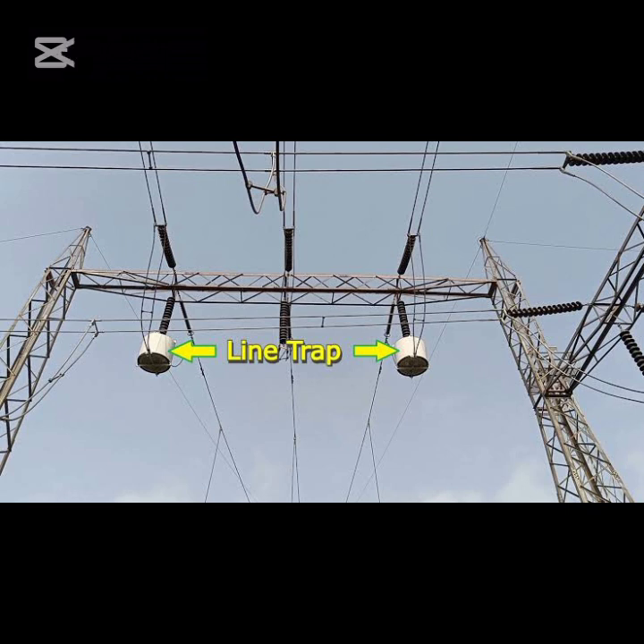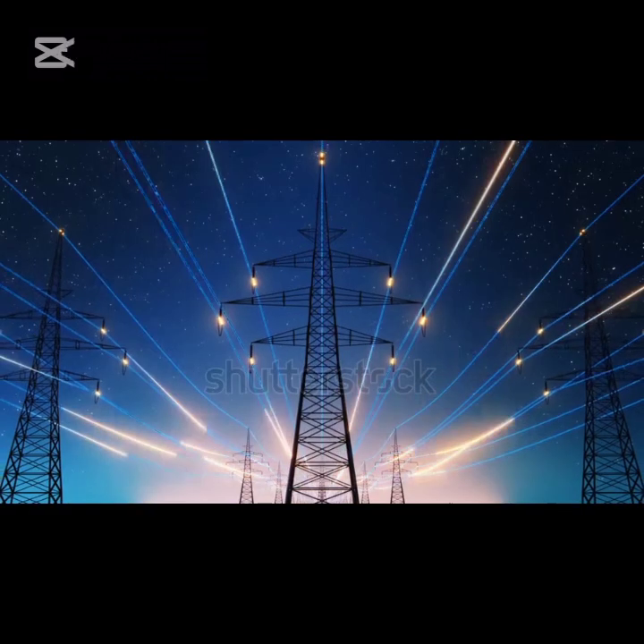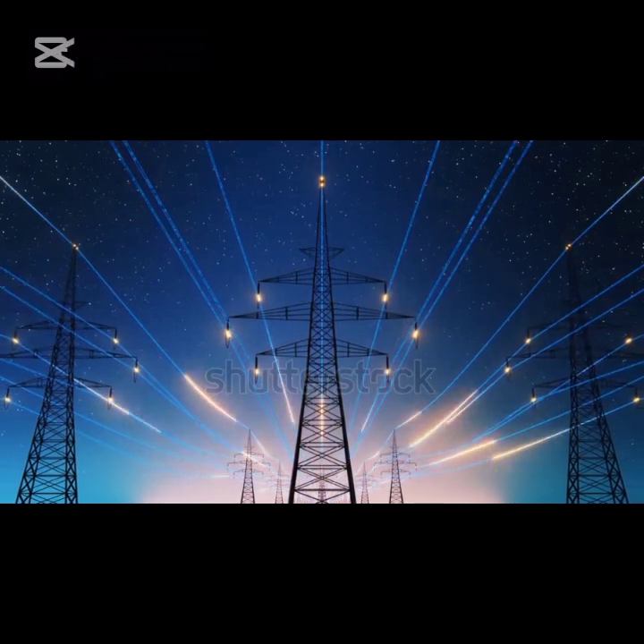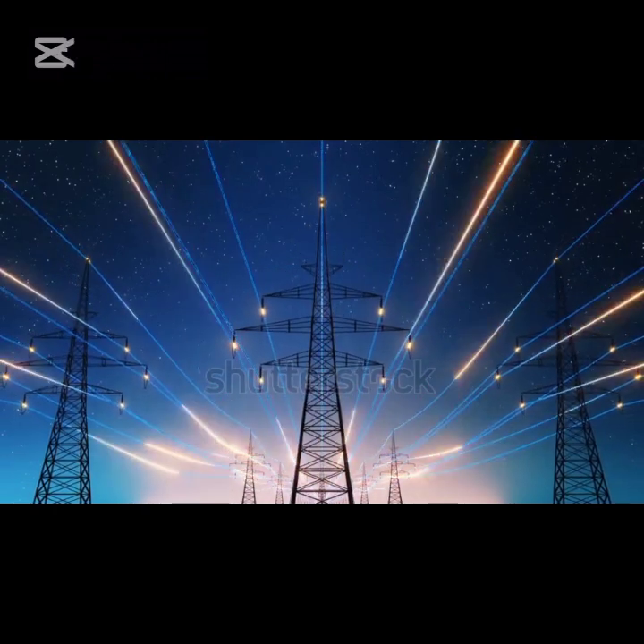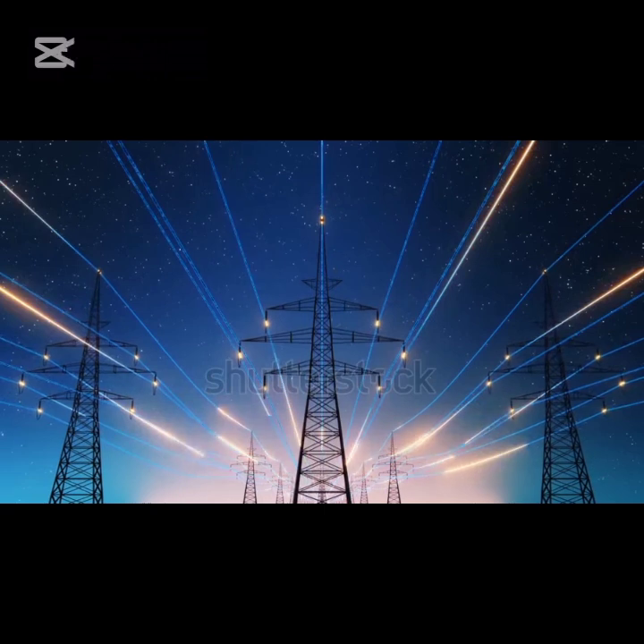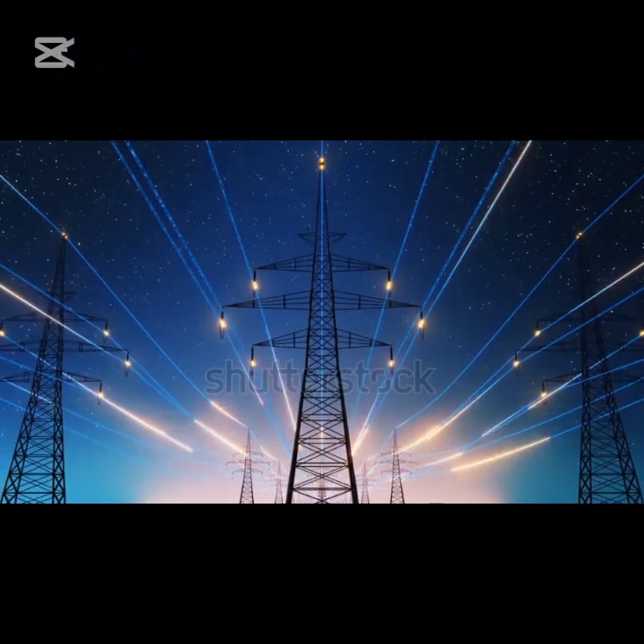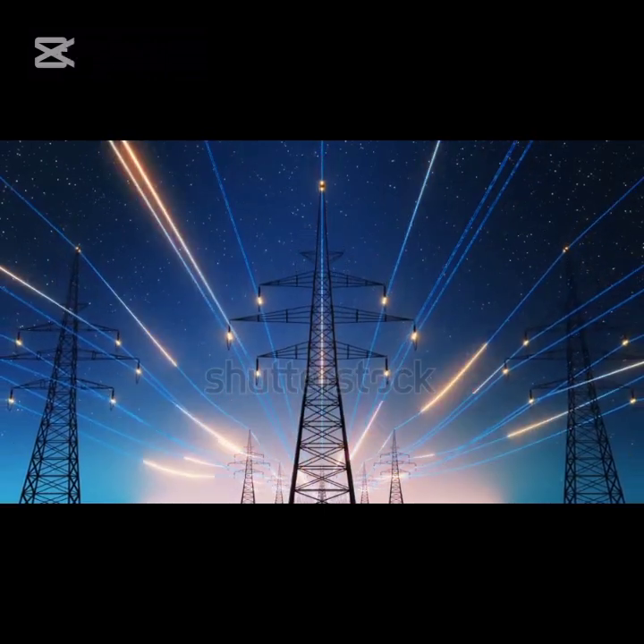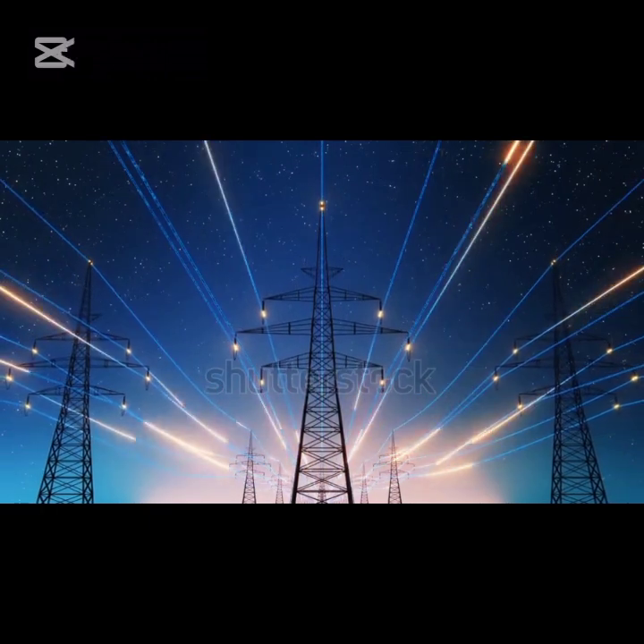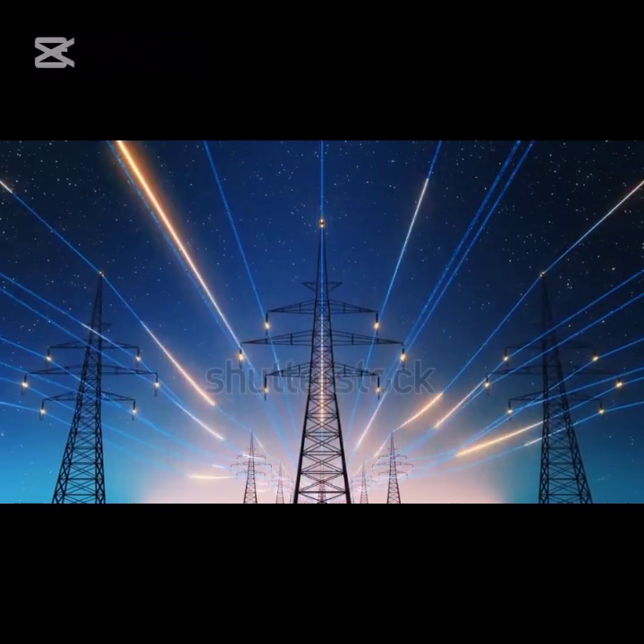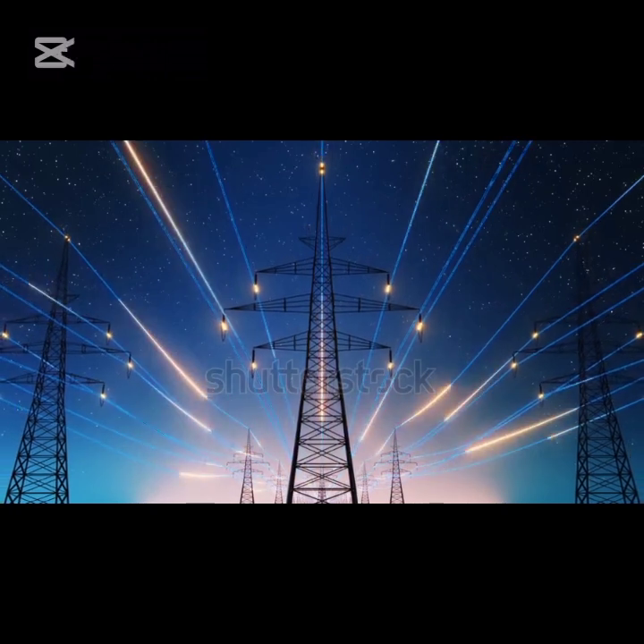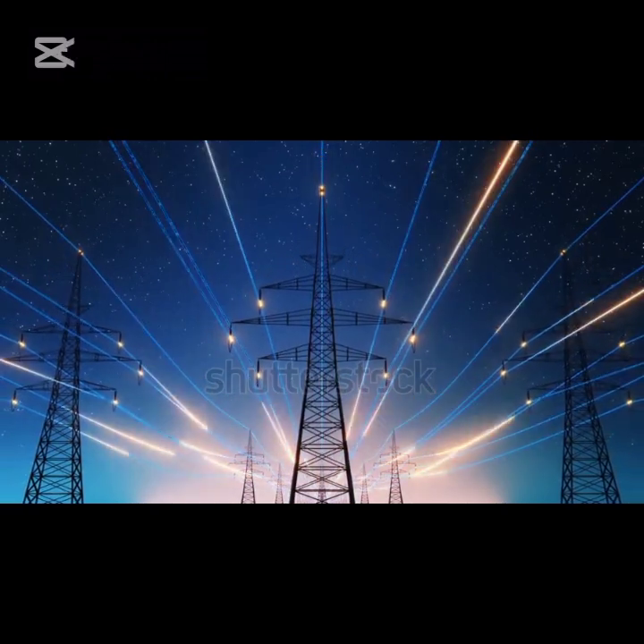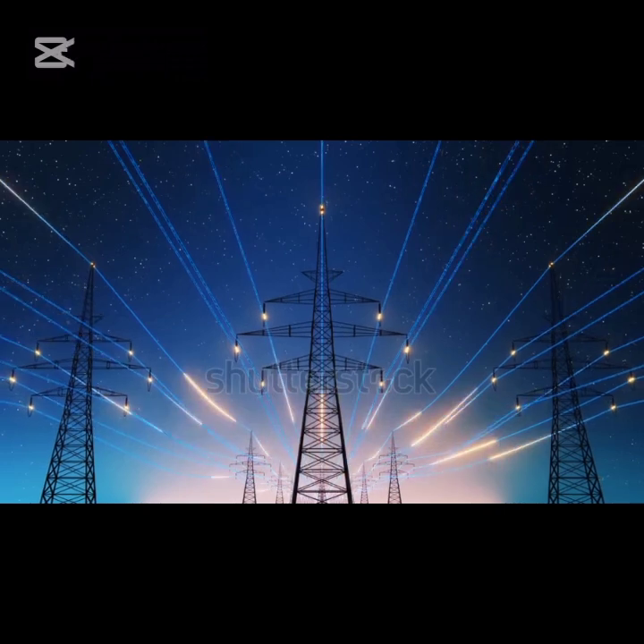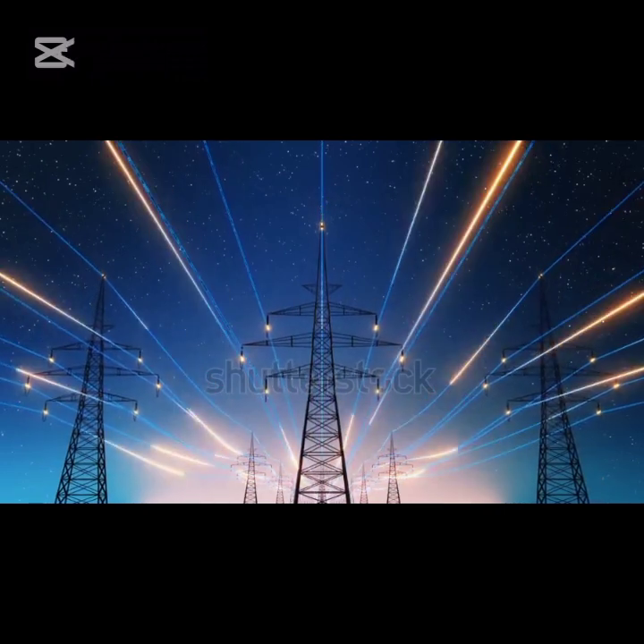In high-voltage electrical power transmission systems, specifically those over 132 kV, the power line carrier communication (PLCC) system is employed for communication between substations. The carrier signals in this system operate within a frequency range of 3 kHz to 800 kHz, while electrical systems function at 50 or 60 Hz. Consequently, when substations communicate using these high-frequency signals, it can lead to damage to switchyard equipment.